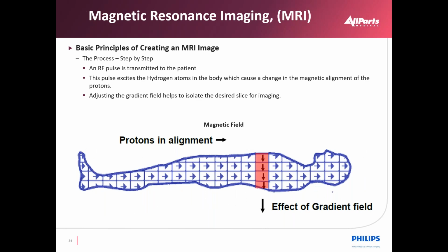So an RF pulse is transmitted to the patient, which momentarily interrupts the magnetic alignment of the protons. To obtain the imaging slice position, a gradient field is applied in 3 coordinates, x, y, and z. When a slice selection gradient field is turned on, it adds or subtracts from the main field in the region of interest. This changes the precessional frequencies of the proton nuclei. A shaped RF pulse is transmitted at the resonant frequency the same time the slice gradient is turned on. Only those protons precessing in a narrow range around the resonant frequency are excited or rotated by the pulse.